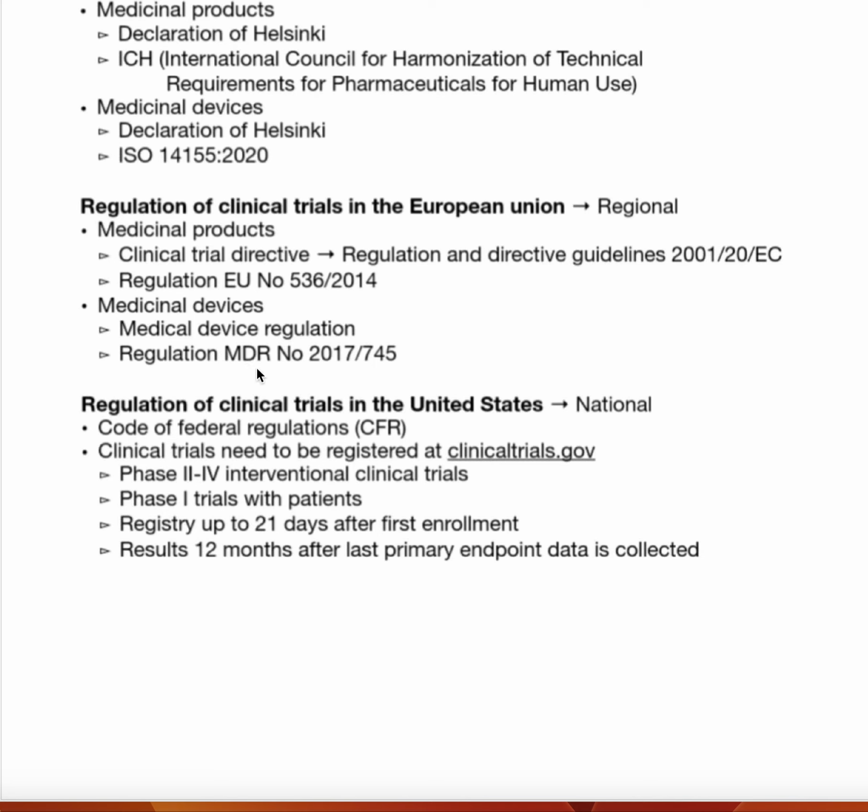It's also here medical device regulation, but the number of it is 2017/745, and unfortunately we have to memorize these things. Okay, so for the regulation that is related to Europe, we have two things: medical devices and medical products. For the products, we said the guideline 2001/20/EC, and we have 536/2014. For the medical devices, MDR 2017/745.